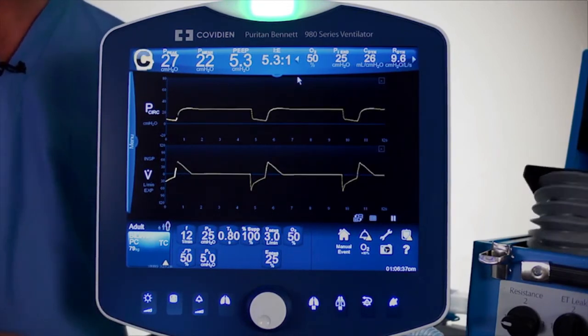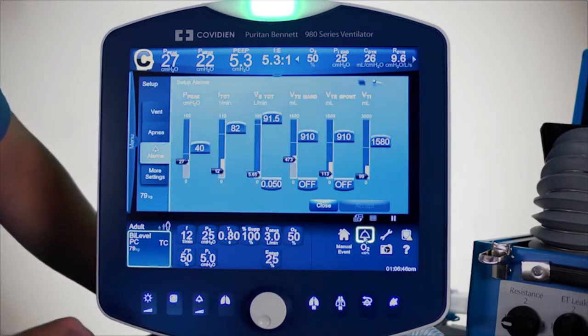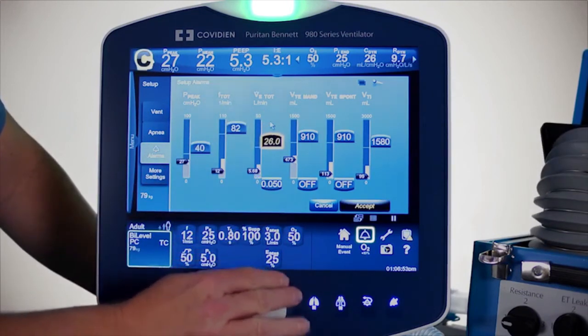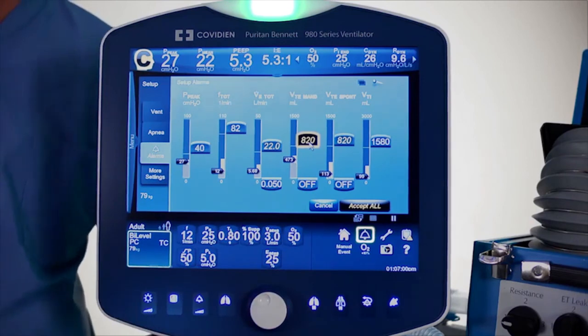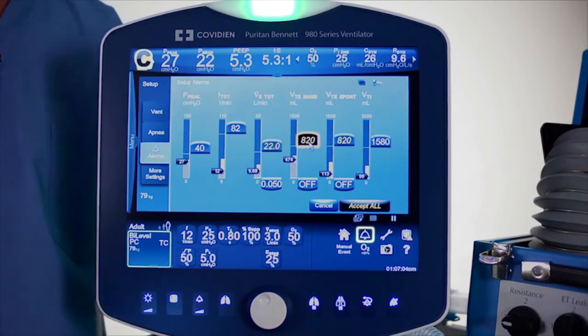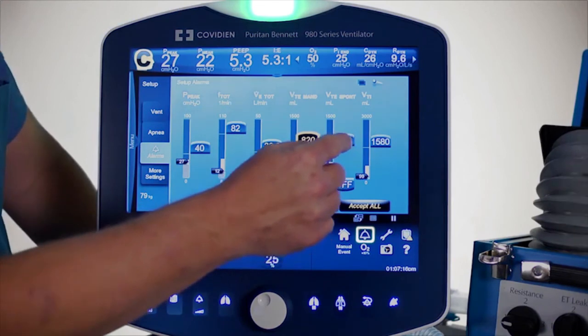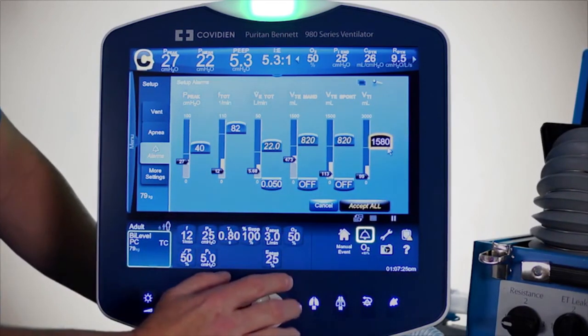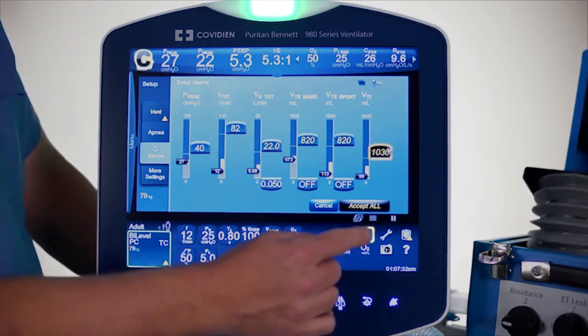The alarms in bi-level mode are your typical ones. Under the alarm screen: high pressure limits, respiratory rates, minute ventilations, and mandatory high tidal alarm limits. Because this is a pressure-based mode of ventilation, it's important to be very careful with the high tidal alarm — if the patient's compliance improves, you want to know right away if the patient is getting a larger volume so you can adjust for a lung protective strategy. You also have spontaneous tidal alarms and a high inspired tidal alarm for tube compensation software. Make sure all those are set appropriately.